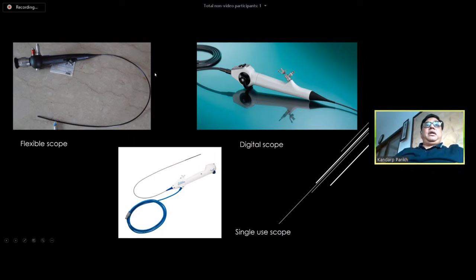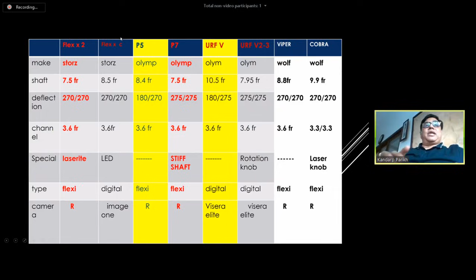We have got Olympus, Karl Storz, and Richard Wolf. All the companies have either their digital scope as well as the flexible scope. The length of all the scope is almost the same. The deflection is the same. The working channel is 3.6 French in almost every scope. The difference is of diameter. The flexible scopes are 7.5 French in diameter, so they can easily go through a 9.5 French ureteral access sheath, while the digital scopes are 8.5 French or 8 French in diameter. So for that, you need at least a 10, 12 ureteral access sheath, so 10 French inner diameter ureteral access sheath.